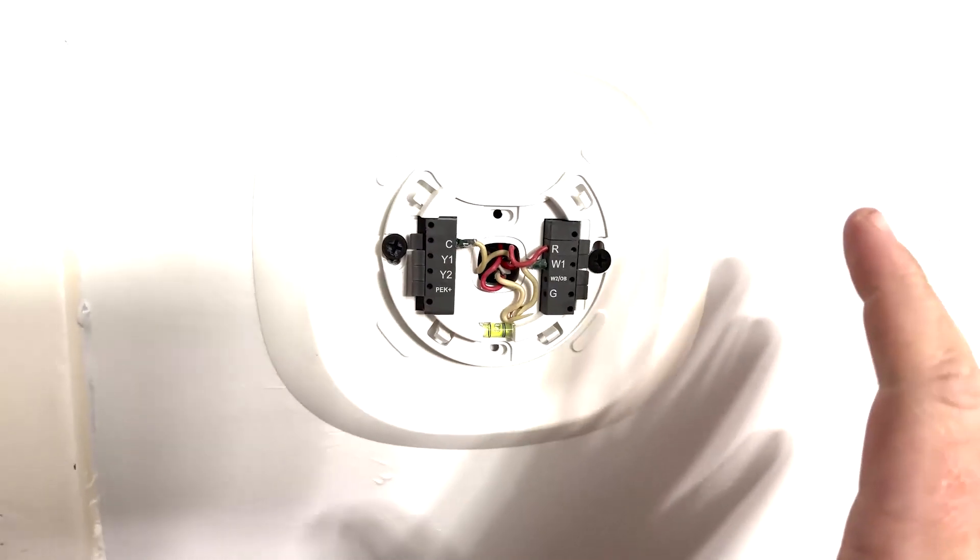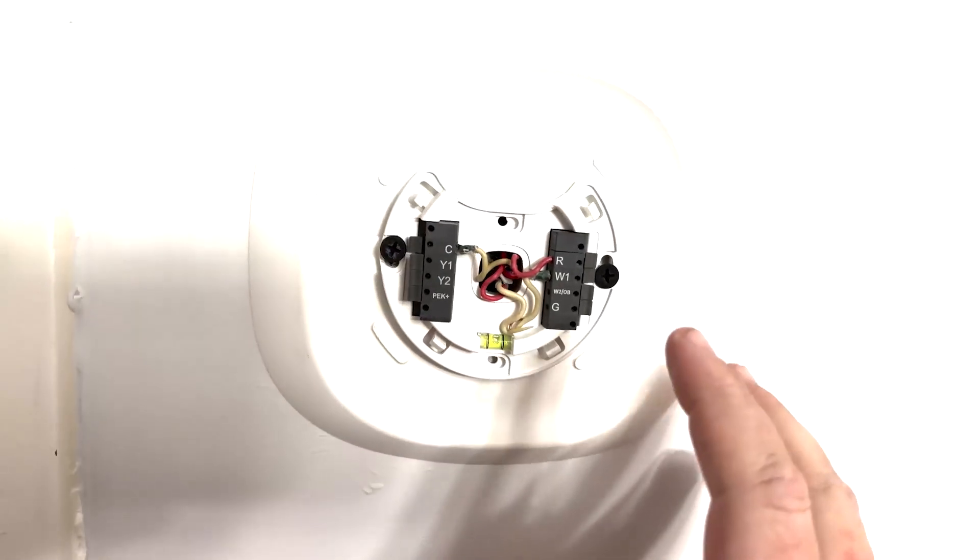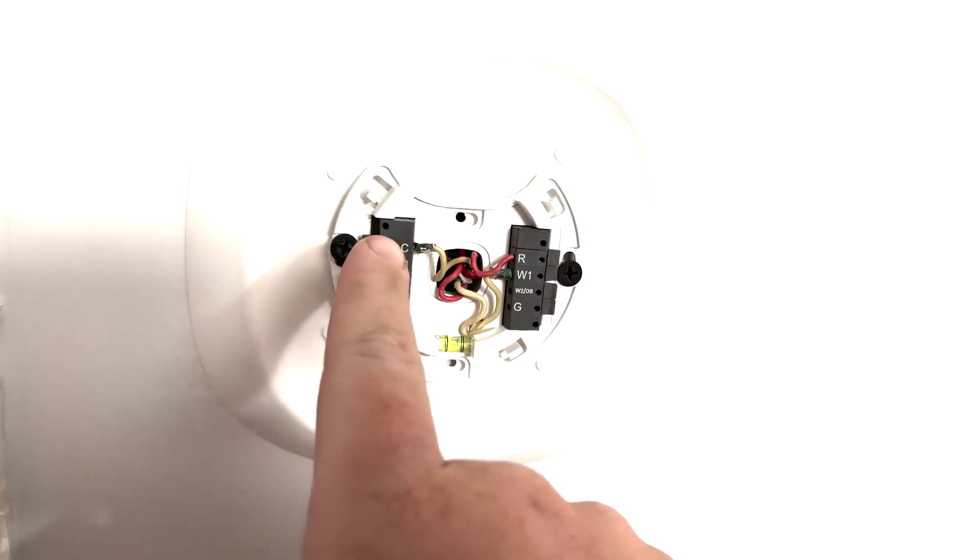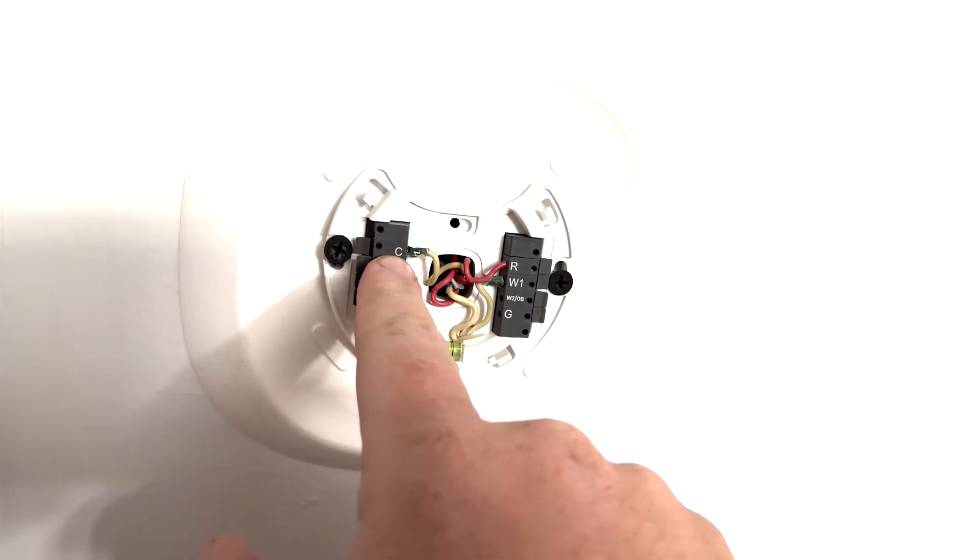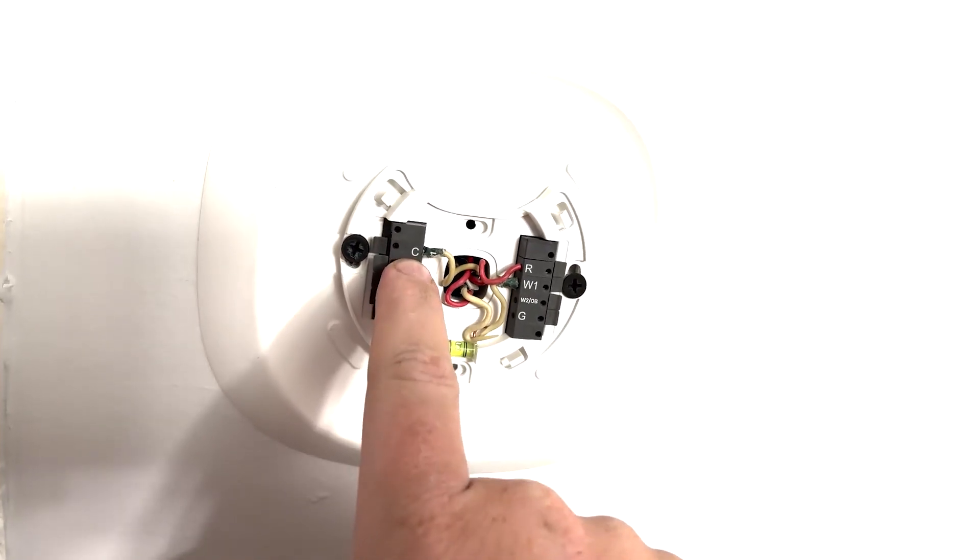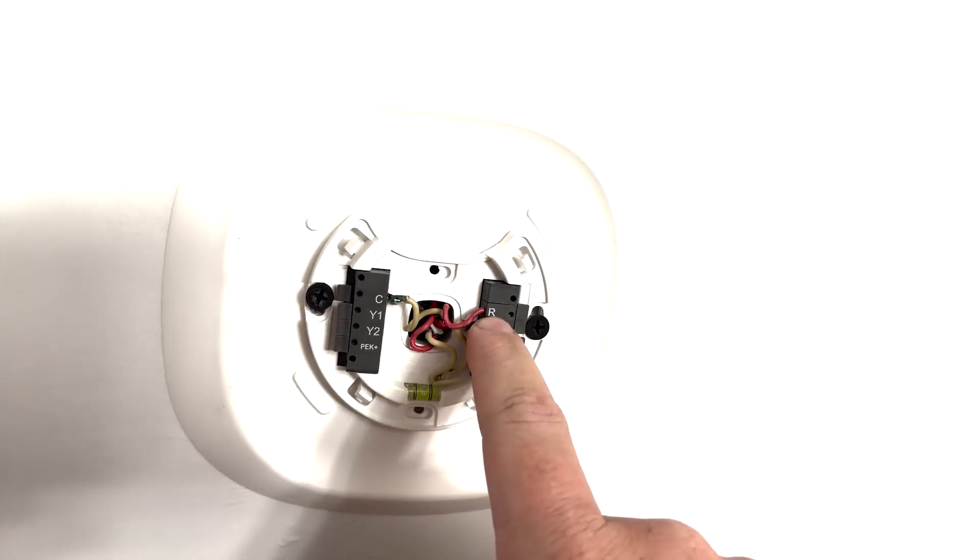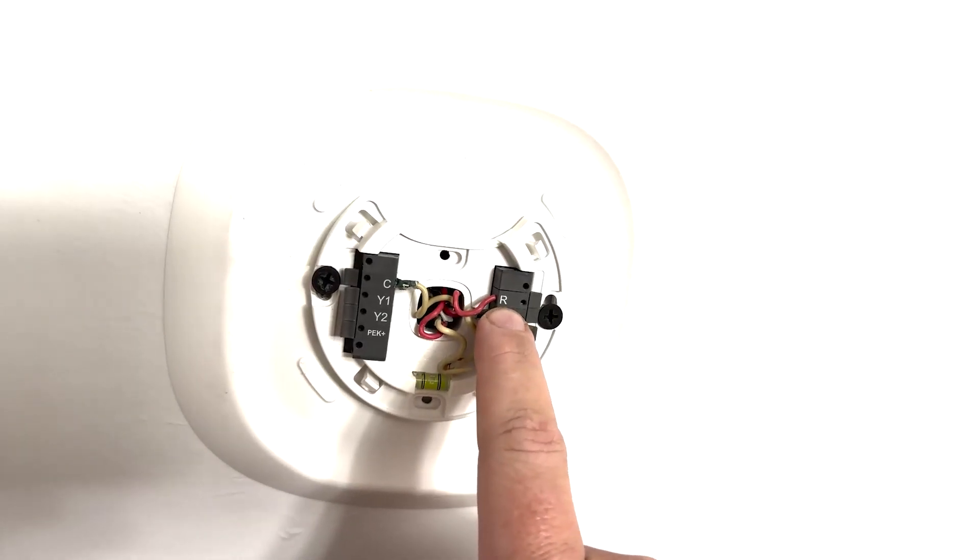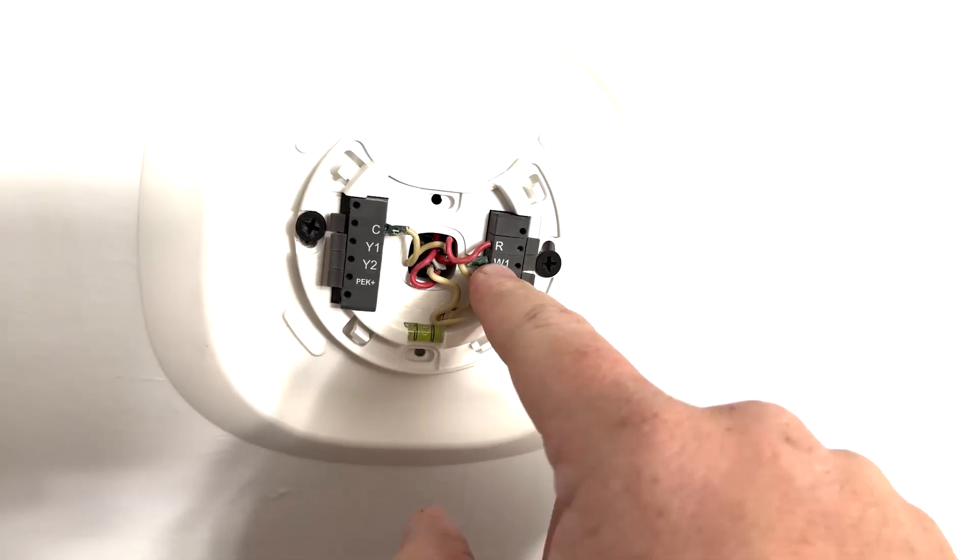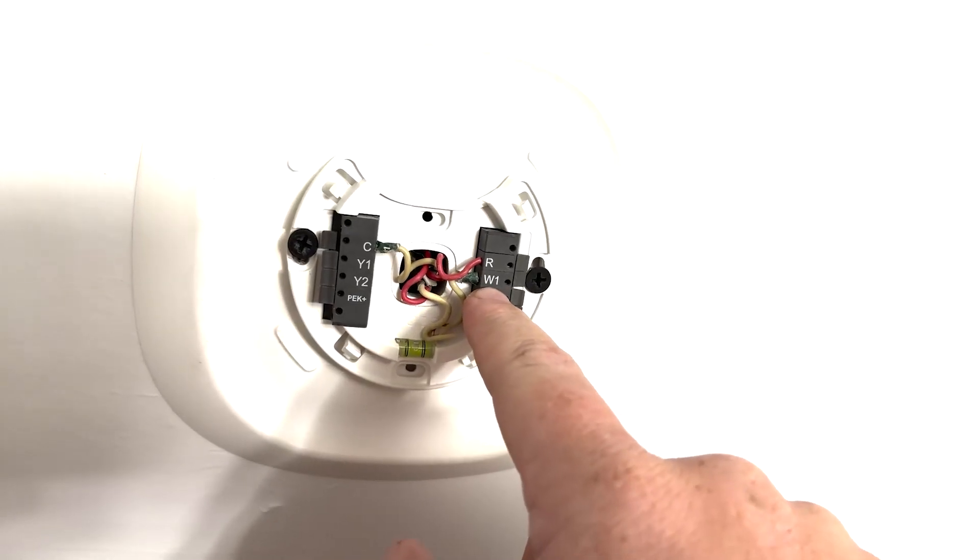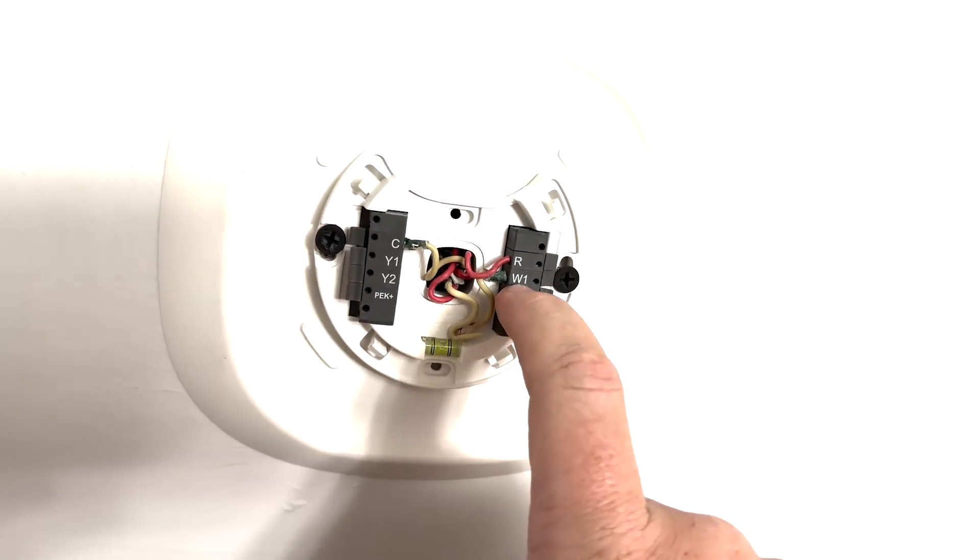So now you're going to look at the thermostat. You're going to have those wires coming up from downstairs. So this is going to be the C-wire that goes down to the transformer. This is going to be the other wire that goes to the transformer. And this wire here is going to be that single wire that goes into that relay into the central terminal on the top.